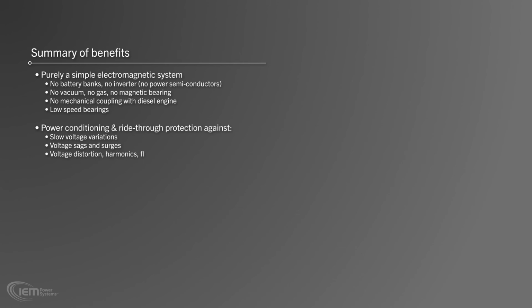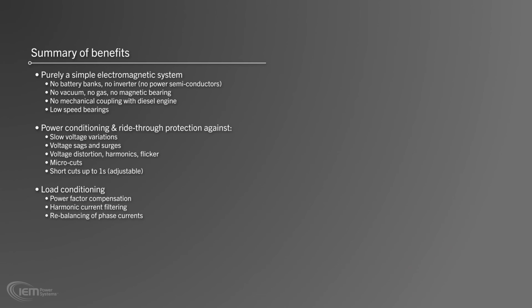The Rotobloc UPS provides voltage conditioning and ride-through protection against slow voltage variations, voltage sags and surges, voltage distortion, harmonics, flicker, microcuts, and shortcuts up to 1 second, adjustable. The RBT system also provides load conditioning with power factor compensation, harmonic current filtering, and rebalancing of phase currents.